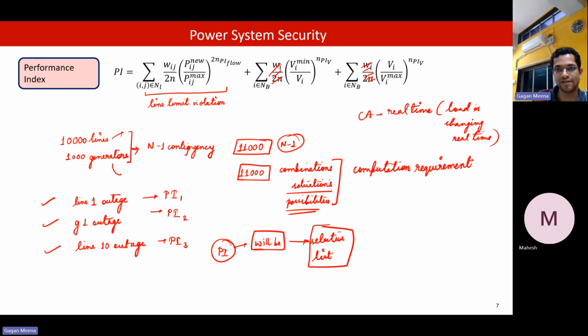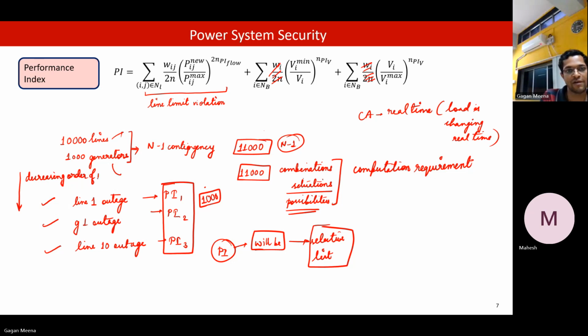We need to reduce this set of n-1 contingencies. How to select that set? For that, we are using this performance index. For each of these 11,000, we can calculate this performance index. For those which have a very high performance index, we can choose some 1,000 or 2,000. If we arrange these contingencies in decreasing order of performance index, then you can select the top N, where N can be anything, say 500. These top N contingencies can be used to do the contingency analysis.